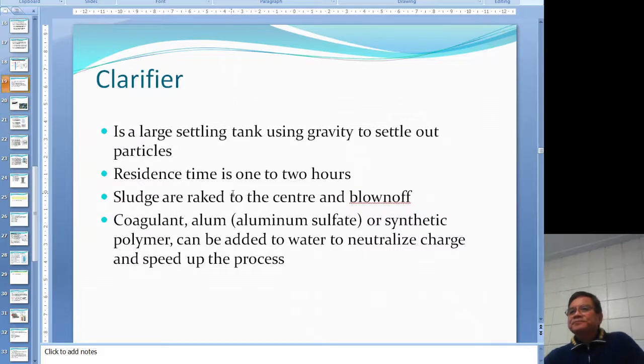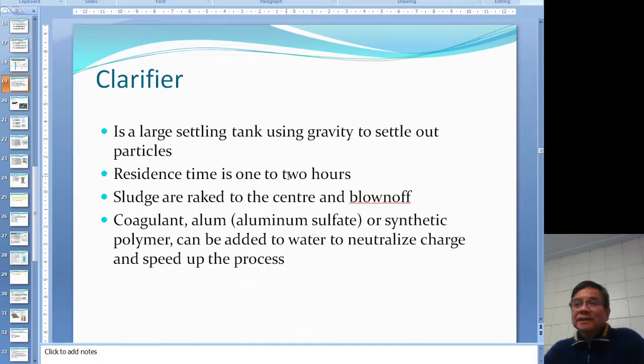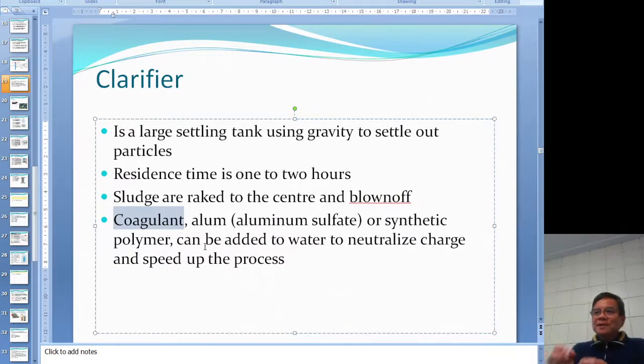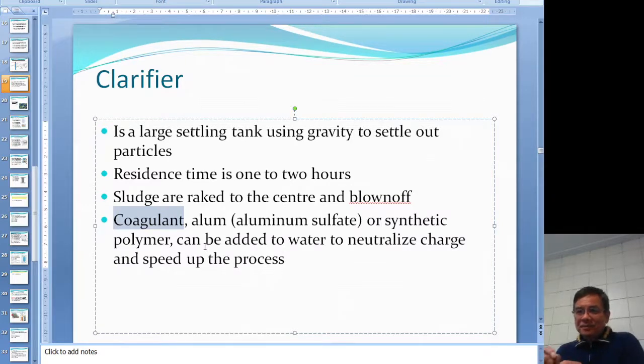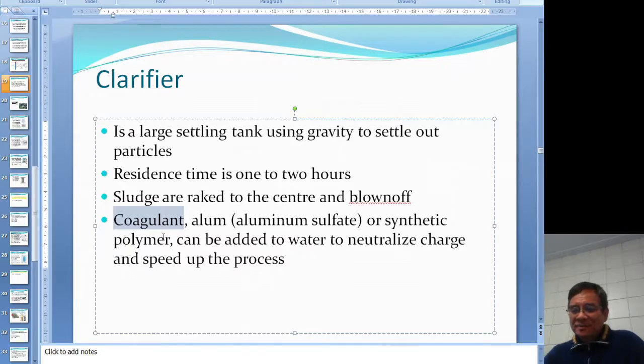In the clarifier, you need some time for settling - most of them only need one to two hours. But the problem is some particles do not settle in one or two hours. So you put in a coagulant - alum is one, or a synthetic polymer. You neutralize the charge on the particles so they group together, sink down, and speed up the process. The coagulant is the chemical that neutralizes the charge so particles group together and sink.